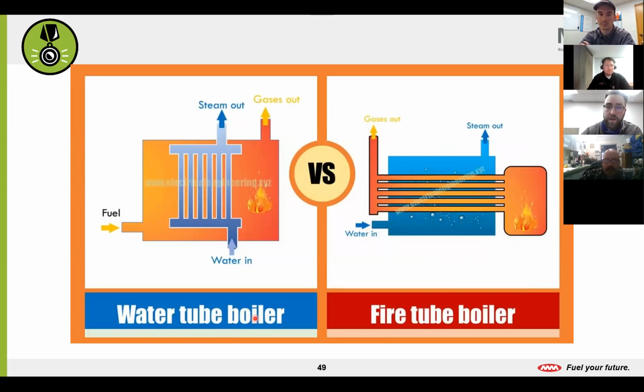With that, I know we were talking about fire tube. There are 2 main types of these kinds of boilers, and there's going to be fire tube and water tube. And we're touching a little bit on the fire tube. And as you can see with fire tube, as I was saying before, the fire, the flame, the heat, and the exhaust is all contained within these tubes. And then the water is actually completely surrounding them and filling up that tank. Let's see here. By the inverse, the water tube boiler is the exact opposite. So water is contained within these smaller tubes, and then the fuel, the fire, the gas, the heat completely surrounds these tubes. Now, looking at these, you would assume, well, it looks like I have more water in the fire tube, so that's probably a higher capacity than the water tube.